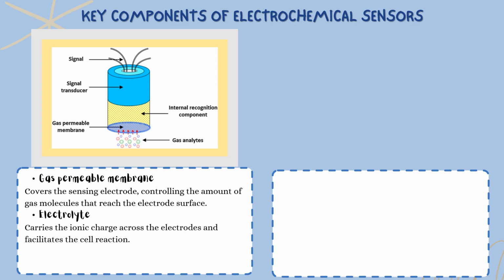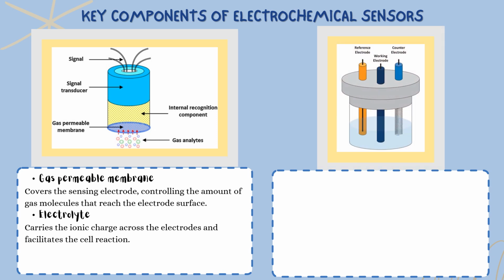Beneath the gas permeable membrane lies the electrolyte, a liquid or gel-like medium essential for ion conduction. The electrolyte connects the electrodes ionically, facilitating the redox reaction necessary for the sensor to function. It surrounds three electrodes: the working electrode, reference electrode, and counter electrode, which are immersed in this medium within the sensing chamber of the sensor.